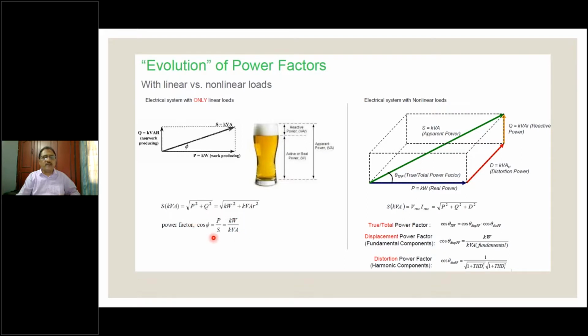This is only the displacement power factor. Here it will be the true power factor, which is the product of the displacement power factor multiplied by the distortion power factor. This understanding is important for you to apply as and when you see a power bill. If you are going to find out why the gap is very high, in spite of the displacement power factor being close to unity, then you will always attribute that to the distortion power factor, which should have been configured in the trivector meter. So let this idea remain with you.